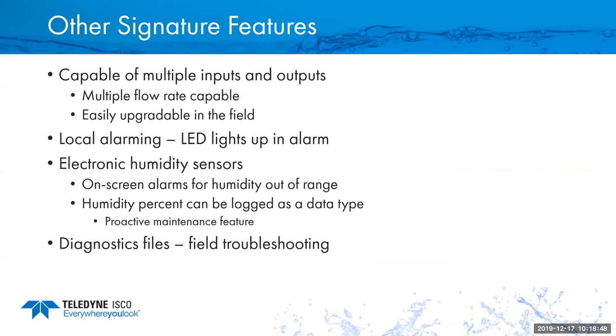Some of the other signature features are the ability to do multiple inputs, outputs, and multiple flow rates. Say you have two ultrasonic sensors and two separate channels, and maybe those two channels converge. You could do a flow rate of the left channel and a flow rate of the right channel, and then in the signature meter you can create calculated flow rates or conditional flow rates. We could actually add together flow rate left and flow rate right to give you a total flow number on your screen. So that gives the ability to create conditional flow rates or combined flow rates.